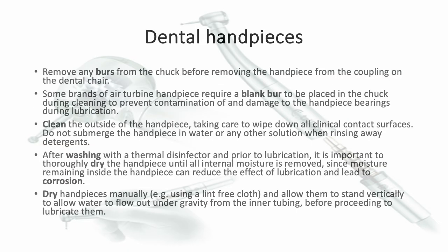Before removing the handpiece after treating the patient, you should remove the burrs. Some of the brands of the handpiece require a blank burr when lubricating it. So, you should place a blank burr in the handpiece during cleaning to prevent the contamination of and damage to the handpiece's bearing during lubrication. When you want to clean the outside of the handpiece, just wipe it down. Do not submerge the handpiece in water or any other solution when rinsing away the detergents.